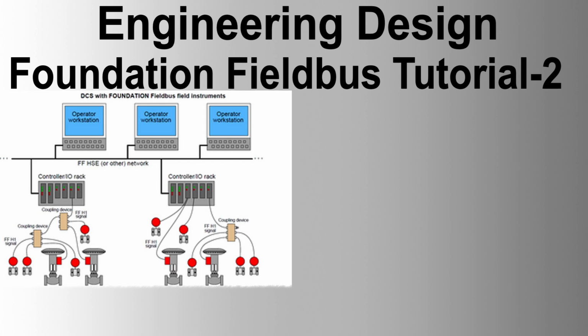Channel value. The channel parameter chooses one of the data values from the transducer block. The channel value is visible in the simulate parameter. Simulation. The simulate parameter allows the AI block to use simulate value and simulate status as channel value and status instead of transducer value and transducer status when enabled.